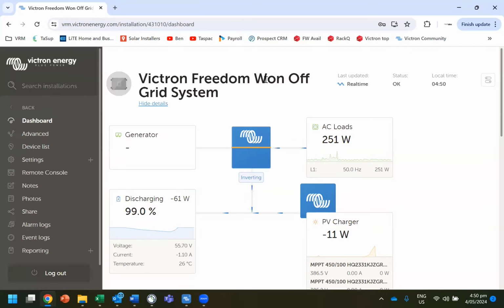Okay, so the main thing you need to set up in the remote console is under services, and make sure that the CAN bus setting is set to 500 kbps, and then the battery will have access to the GX device, which in this case is a Color Control GX.